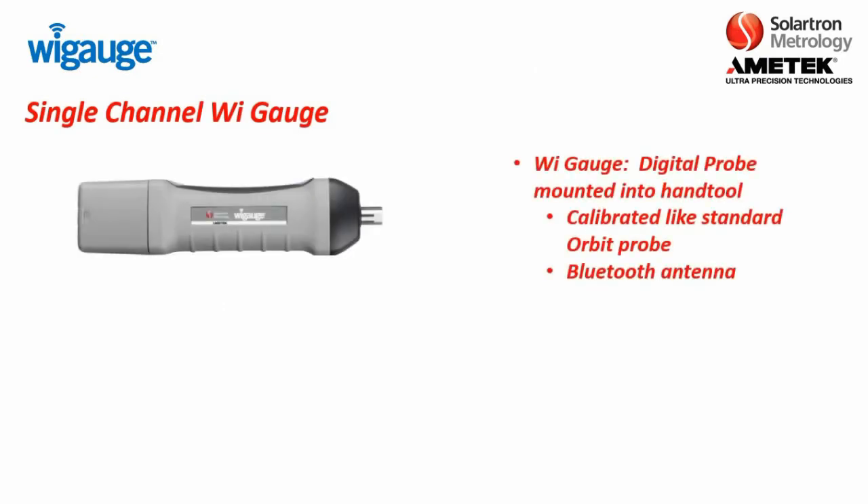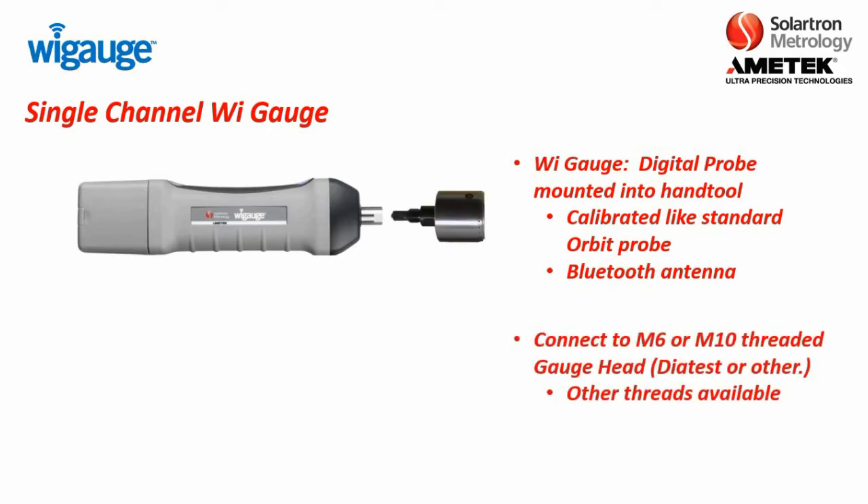First, we will discuss the single-channel WiGauge. The single-channel WiGauge is basically a digital probe that is mounted into a hand tool. It is calibrated like a standard Orbit probe, only this one has a Bluetooth antenna. At the end of it, you basically have an M6 or an M10-threaded gauge head for Diatest that you screw into the end of the WiGauge, which comes into contact with the Solartron digital probe, allowing you to take measurements.